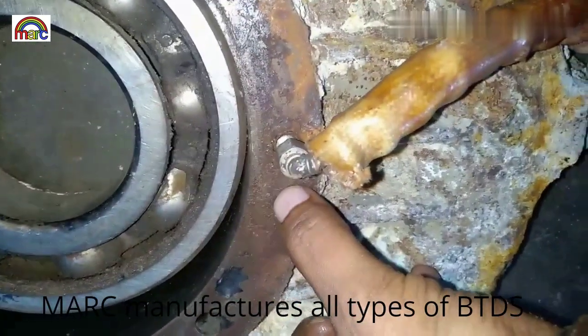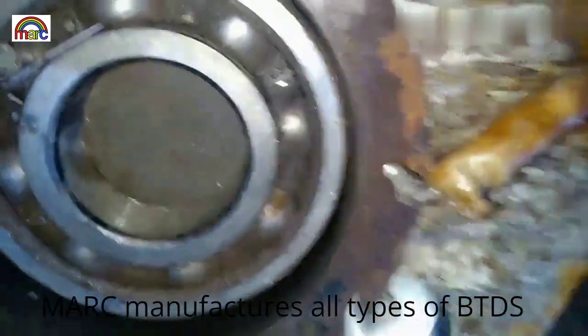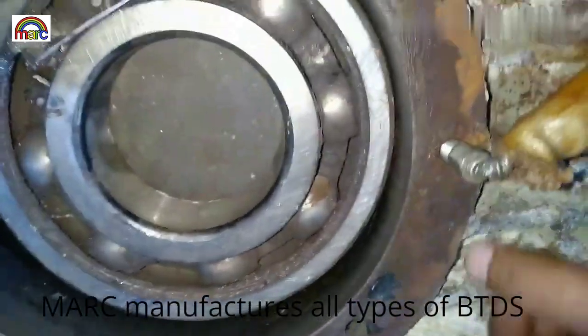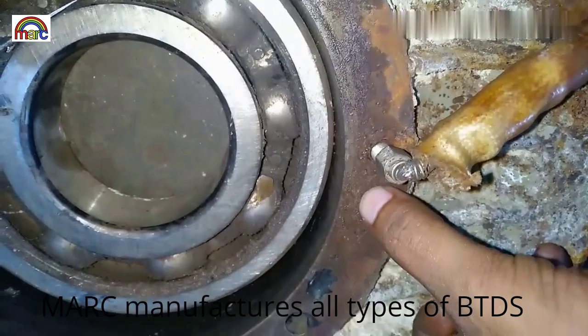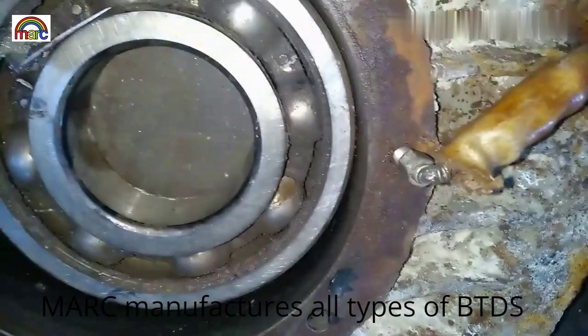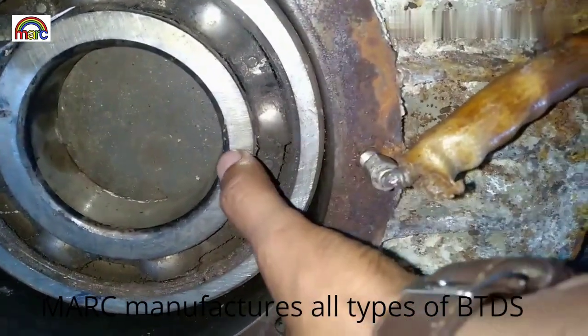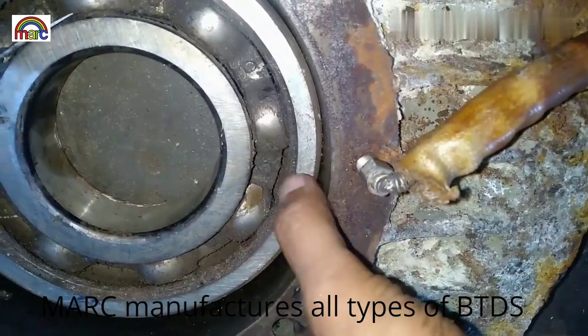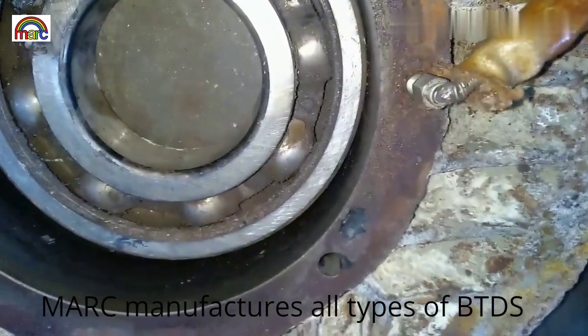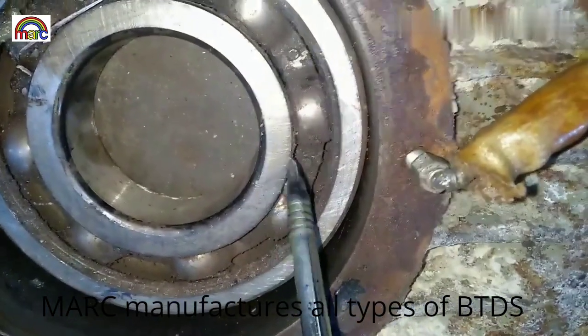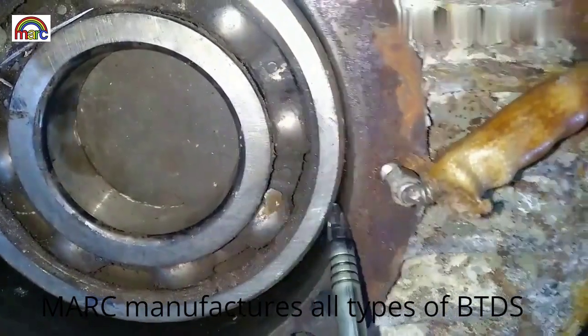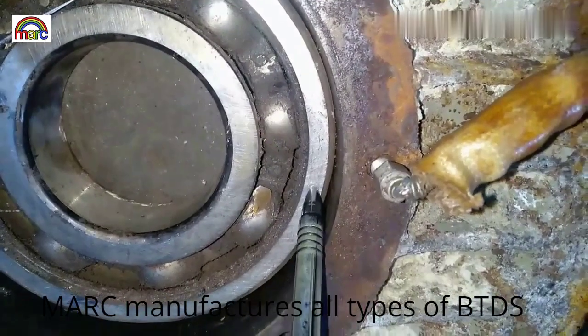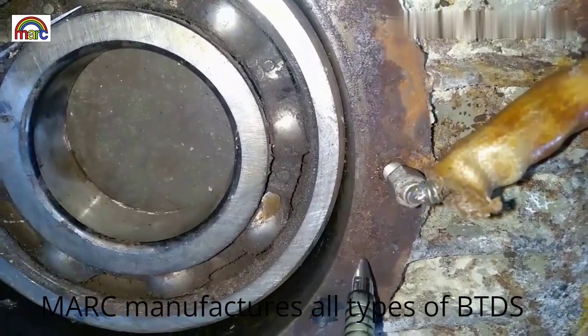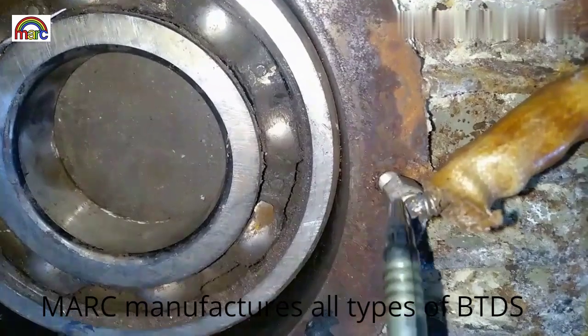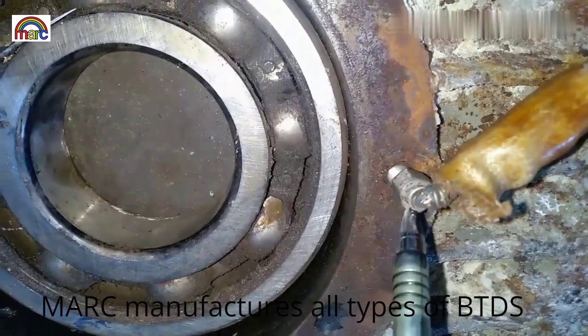Please know that this is not the only way of fixing BTDs. There are many other methods by which BTDs are fixed on the bearing housing or the end shields. Every manufacturer has different methods of fixing, and there are many types of probes also. Some are of 6 leads, some are of 3 leads. Depending on the designer and the application, the probe design may change.